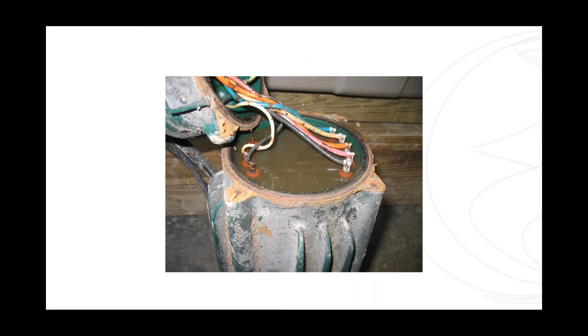If you're using a pump in a pit and you don't use a junction box, and instead just pull the cable up, put some wire nuts on it and some black electrical tape, this is what can happen. This is a good reason to use cord grips. Many of our pump power cords can wick moisture over time, and here's exactly what can happen: I have the cap of this pump off, and it's filled with water right up to the top of those through-wall terminals with all the electrical wires connected. When water gets up to that point, it's going to short out all of our electrical connections.